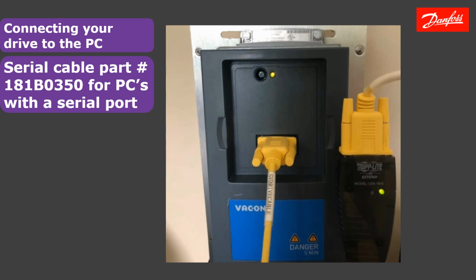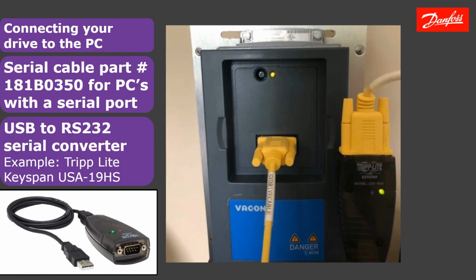In the event that you do not have a serial port you're connecting to, the more likely event would be that you're using some sort of USB to serial converter. So here I have a USB to 232 conversion tool. Once you plug that device into the USB port of your computer, it will be assigned a COM port, and we have to match that COM port in the software in order to establish the communication.